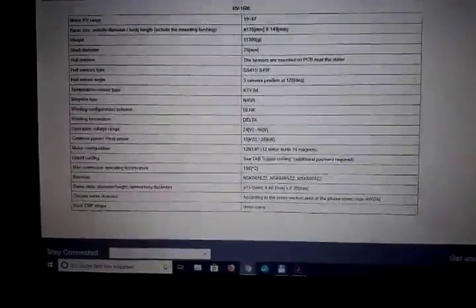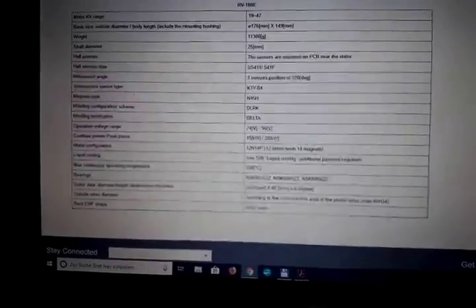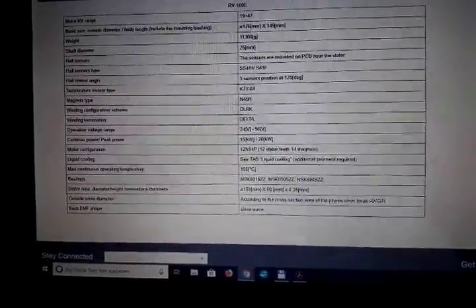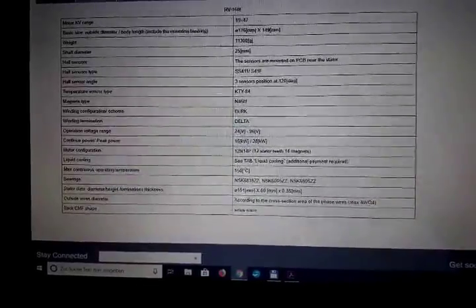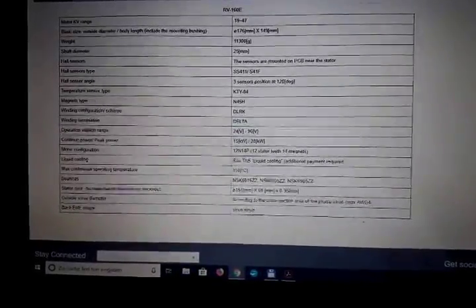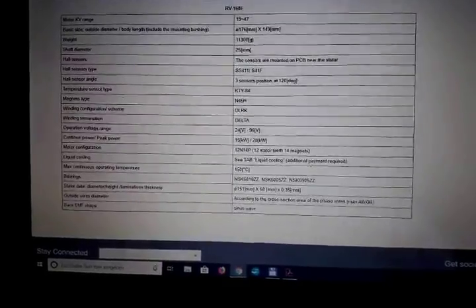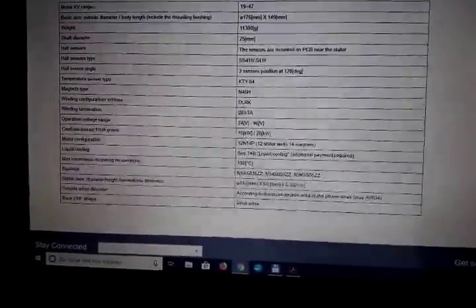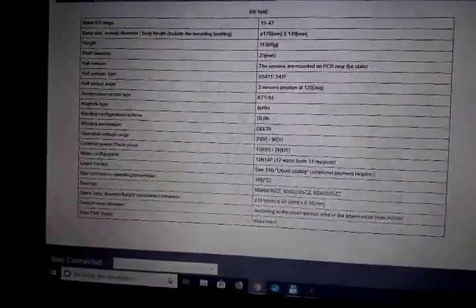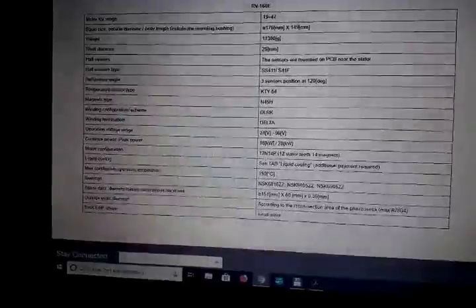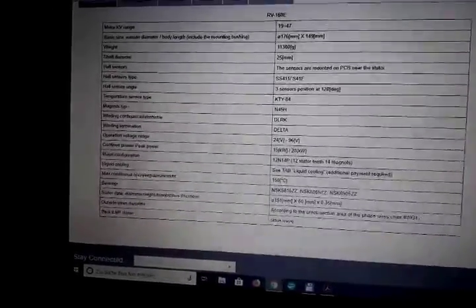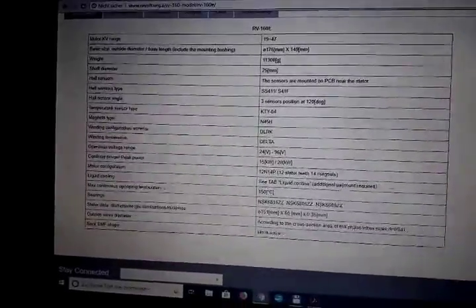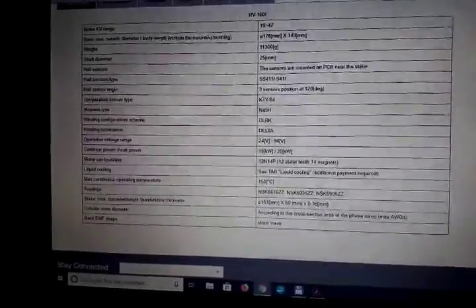So first of all, as I said before, it's water-cooled, which is a good idea to lower the temperature of a copper winding package because copper has a positive temperature coefficient. It increases its resistance by 0.3% or 0.4% for each Kelvin. But on the other hand, I never experienced any critical temperatures in the stator. So I don't know whether it's worth the additional effort for a liquid cooling system.